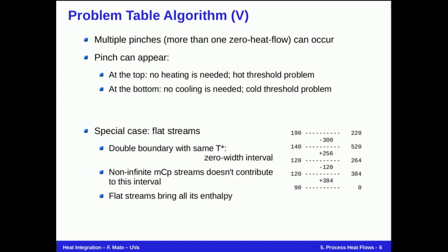Some particular cases: multiple pinches, where more than one zero heat flow can occur. The pinch can also appear at the very top, that is, no heating is needed. This is a hot threshold problem. Or at the bottom, where no cooling is needed. It's a cold threshold problem.